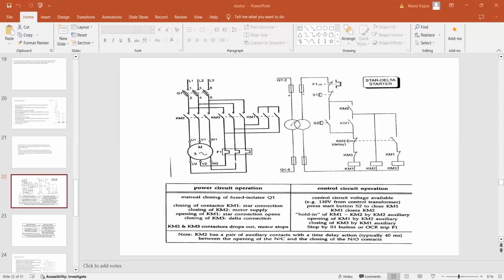Opening of KM1, star connection opens, and closing of KM2 and KM3, delta connection closes. KM2 and KM3 contactors drop out, then your motor will stop, because in the end the motor is running in delta, right? So KM3 and KM2 have to open for stopping the motor. For that they have put the OCR here also, you can see F1 is OCR as well as the stop switch.